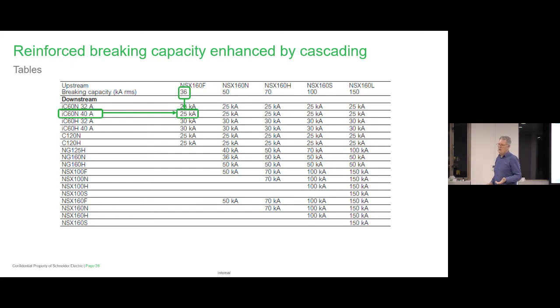And we've pushed this really hard. We struggled in the early days of cascading, of the new technology coming in 20 years ago. I shouldn't show my age, but 20 plus years ago, we were struggling to bring this principle across to electrical engineers, because electrical engineers know this is a prospective fault. We want a circuit breaker that can handle that fault. No, that's what we want. But we can do this. No, but we're going to guarantee it. But the industry has accepted it now because it's money. It's money, and it's real, and it's tested, and it can withstand it.